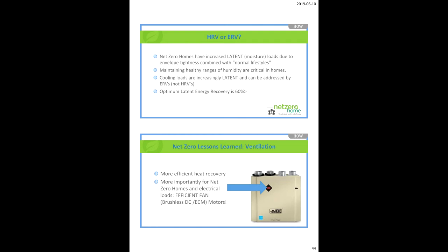No. An ERV allows you to continue to use your air conditioning, because when the air is already being pre-cooled by the air conditioner, it vents the cold air out and actually pre-dehumidifies the incoming air. Some of the studies at the CHT home said it adds about 20% efficiency to the air conditioner over and above an HRV. So again, something that we're seeing.